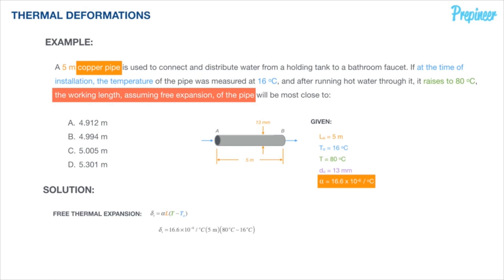With the coefficient of thermal expansion now defined, we have all the variables we need. All we need to do is simply place those into our formula, pump them into our calculator, and determine that the change, the thermal expansion, the thermal deformation of this copper pipe is going to be 0.0053. So that's the thermal expansion, the change in length. But we're not done here.